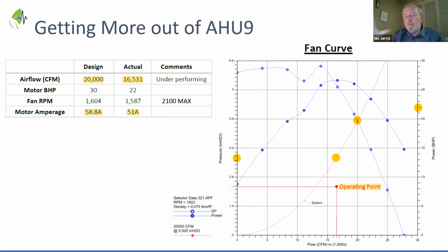And maybe the other big example is you need lead time to be able to get this done. If your project's getting underway and you discover this, it's too late to do the kind of investigation and get the system up to snuff so it can play its role. So here, a 20,000 CFM system is only delivering 16,500 CFM. Strangely, the motor amperage and the motor brake horsepower are surprisingly high for that. So we have a system here that's working really hard to deliver not very much.